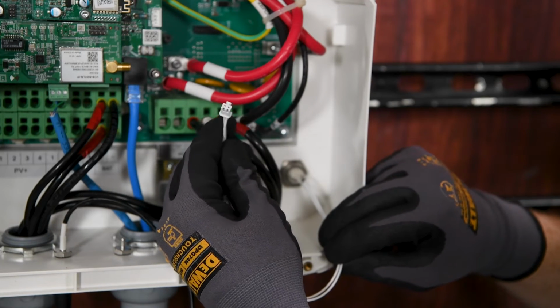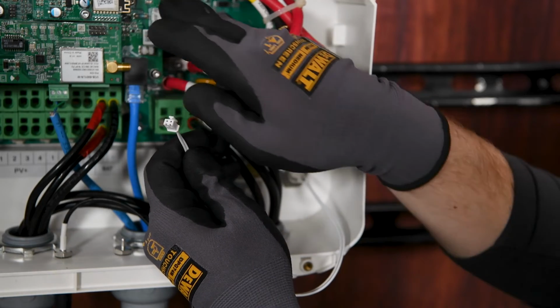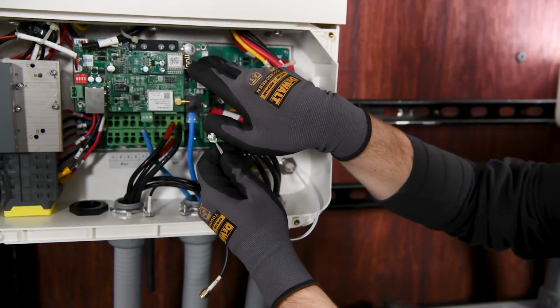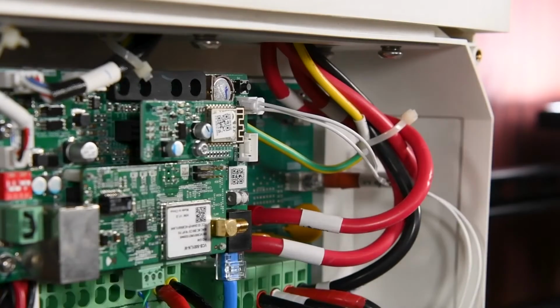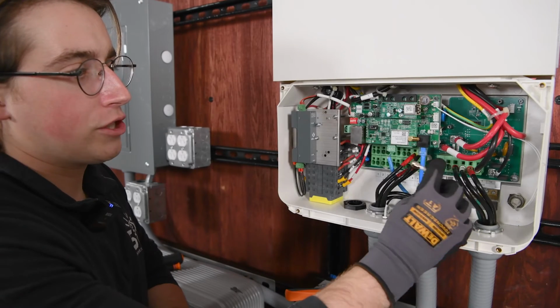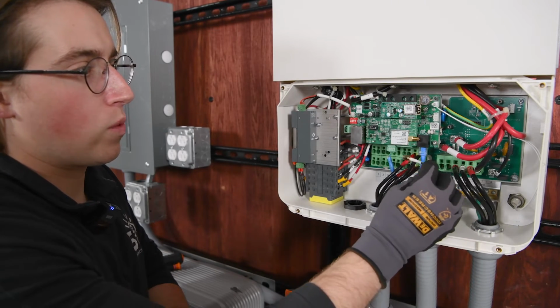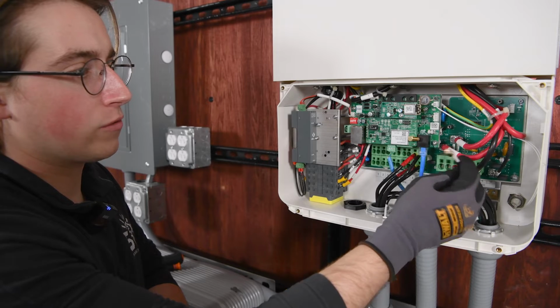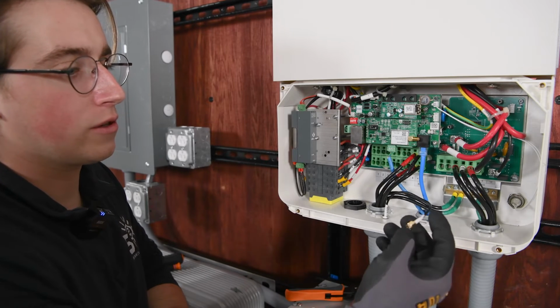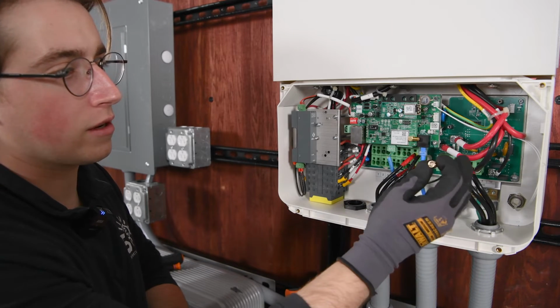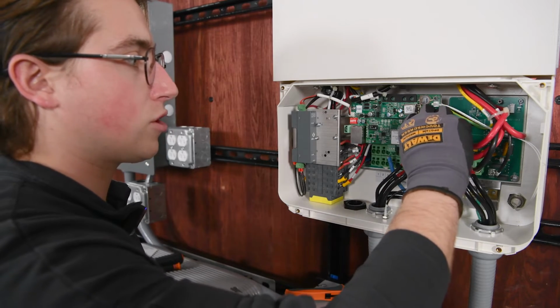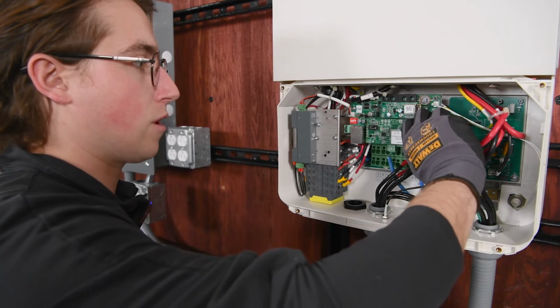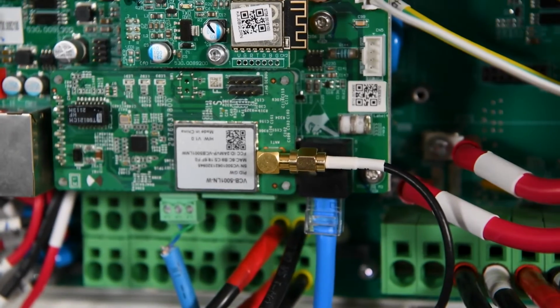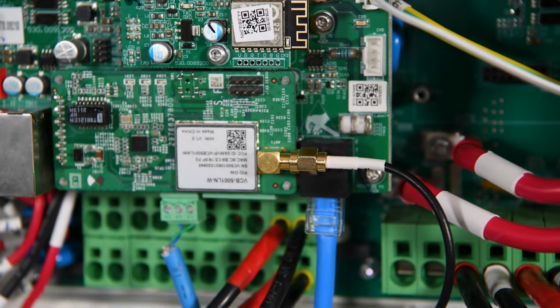Next, we have our 2-wire connection, and this will connect to this 2-wire pin up here at the top of our communications board. During the installation, I disconnected this Wi-Fi antenna connector. The reason for that was just to make the install a little bit easier, so we're going to reconnect that. It should be pre-installed whenever you take the inverter out of the box. Again, I just removed it to make the install of the wires easier.